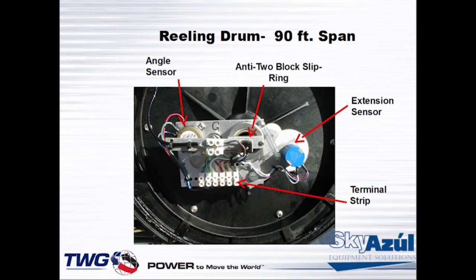And you're either going to click or drag like we talked about on the clutch yesterday. And just make sure the clutch is working. Bring it back exactly a half a turn. Exactly a half a turn. And then when you measure the voltage that shows on your card at 0.15 to 0.35, that will set up the 0 point for your extension, okay? That sets up the point.